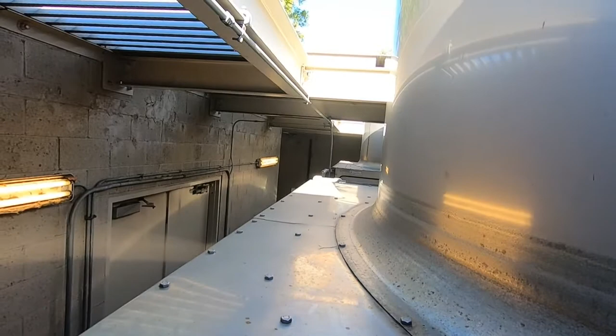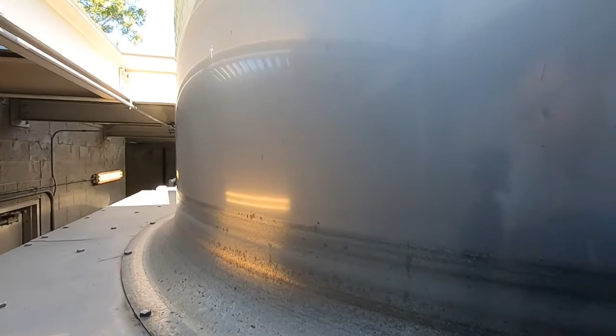It's pretty straightforward, nothing too crazy, but we need a couple guys here—this isn't a one-man show. I've got to build a gantry so we can lift the fan blade up. I've got unistrut down, and I'll build a gantry coming off here and over the top, with a hoist system so we can pull the fan blade up off the shaft. That way we can slide the shaft back into the new bearings, then lower the fan blade back down once it's out of the way.